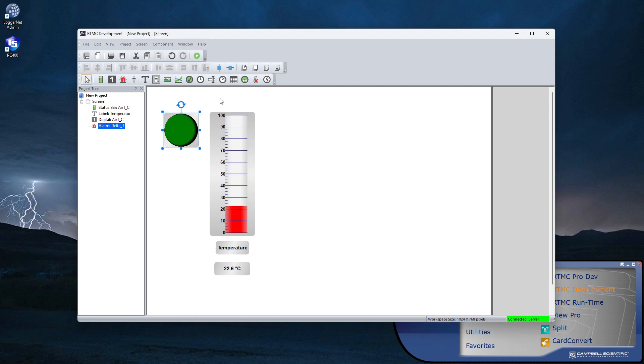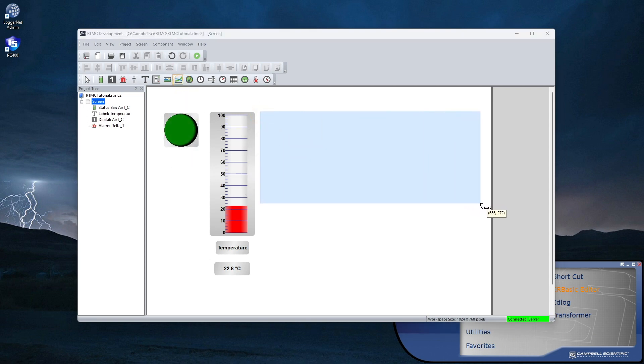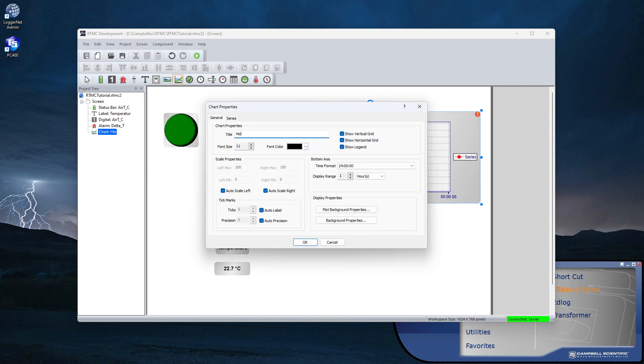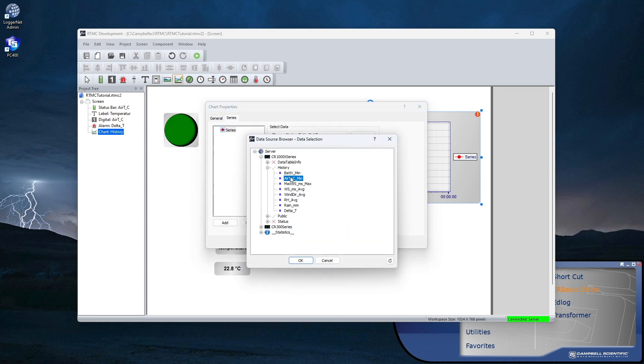Next, I'll add a chart to display historic data. The previous components — thermometer and digital display — display data from a single point in time, and the public and status tables work well as data sources for this type of component. But if I want to show some history of my data, I'll pull that from a stored data table. The chart has properties, and the Series tab is where I select the data source. This time I'm displaying data from a stored data table, not the public table. Here I pick the max, mins, averages, etc. Click the Add button to add additional traces the same way.